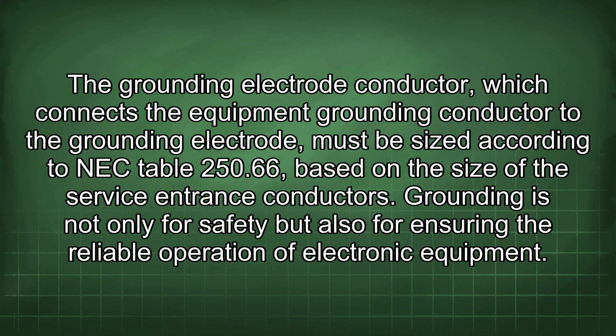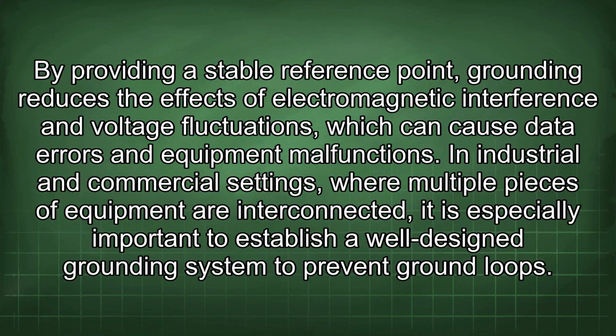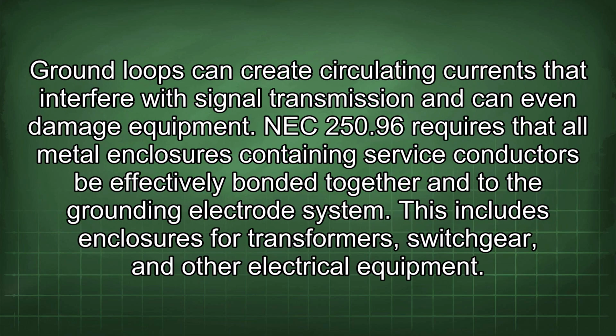Grounding is not only for safety but also for ensuring the reliable operation of electronic equipment. By providing a stable reference point, grounding reduces the effects of electromagnetic interference and voltage fluctuations, which can cause data errors and equipment malfunctions. In industrial and commercial settings where multiple pieces of equipment are interconnected, it is especially important to establish a well-designed grounding system to prevent ground loops. Ground loops can create circulating currents that interfere with signal transmission and can even damage equipment.